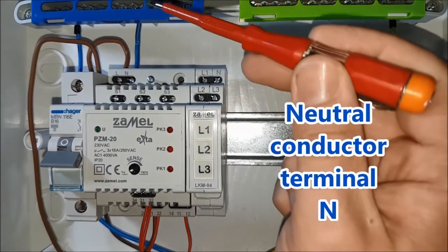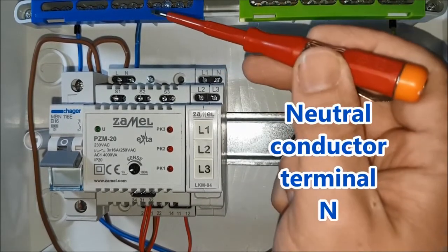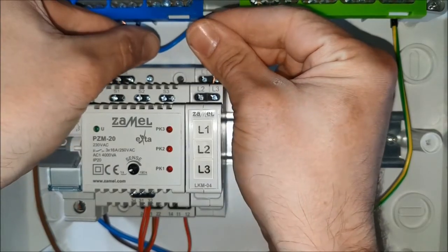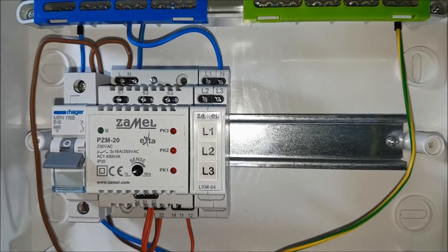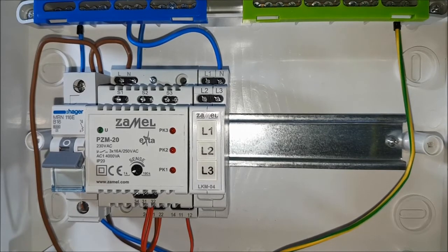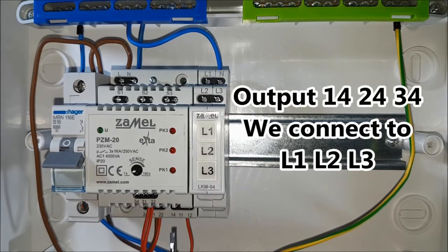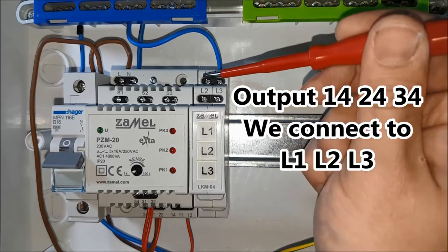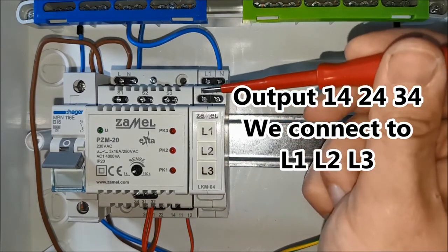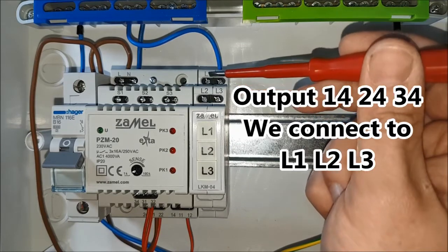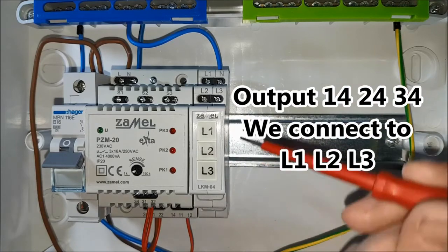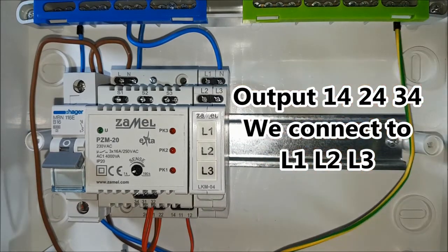The neutral wire goes to the N terminal of the power indicator LKM-04. The relay outputs, that is, terminals 14, 24 and 34, will be connected to the inputs of the receiver supply phase marked as L1, L2 and L3. These outputs can, for example, supply power to pumps, alarm systems or other automation components.